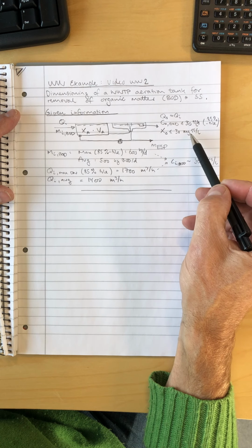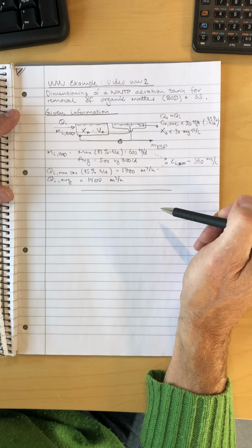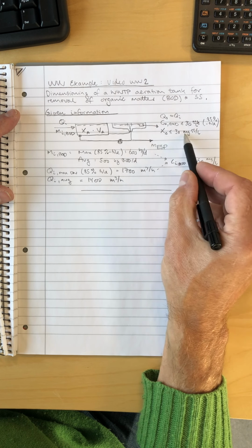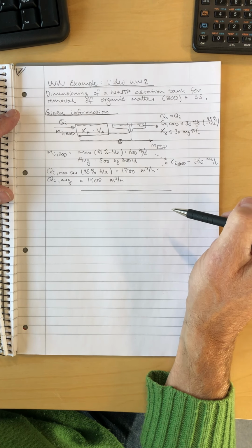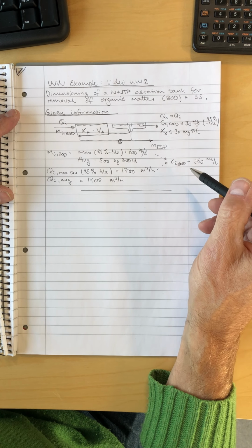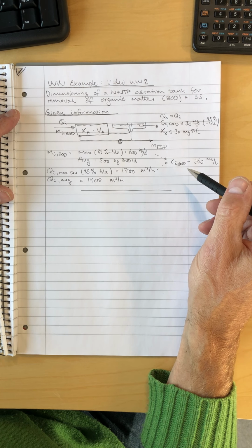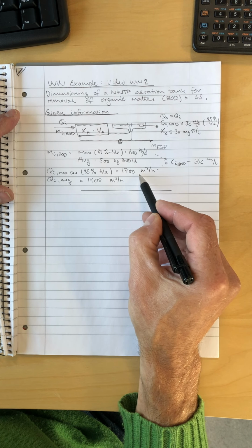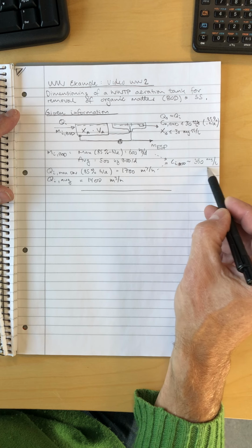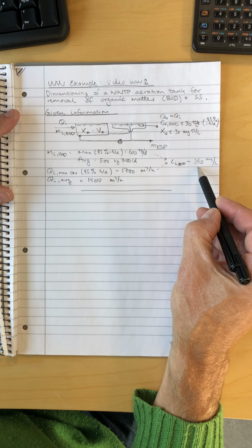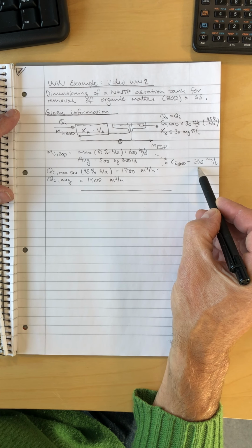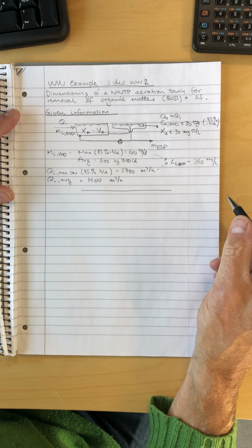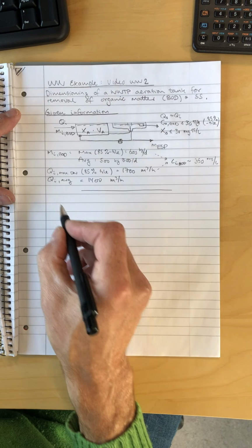I have outlet criteria for BOD less than 30 milligram per liter as an 85 percentile, and also an outlet criteria for suspended solids. If I'm looking at the load of organic matter and the flow, I could calculate approximately the concentration at the inlet. So I see with 350 milligram BOD at the inlet and 30 at the outlet, I need more than 90% efficiency, 90 to 95, maybe 95% efficiency.